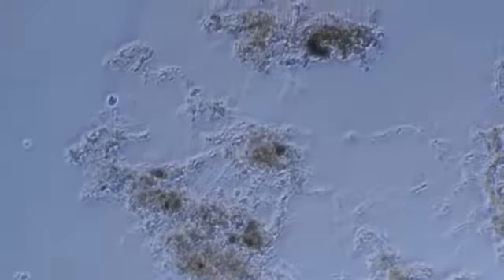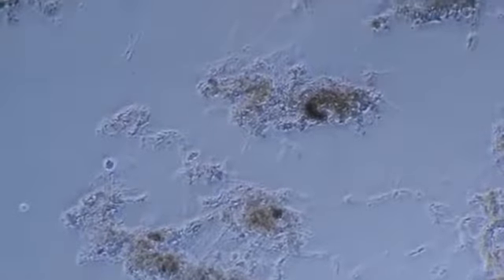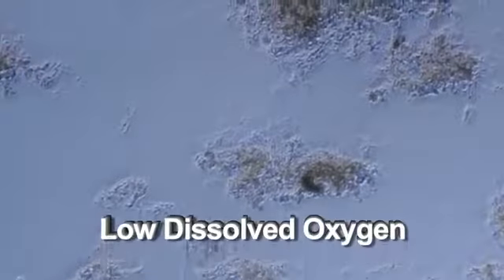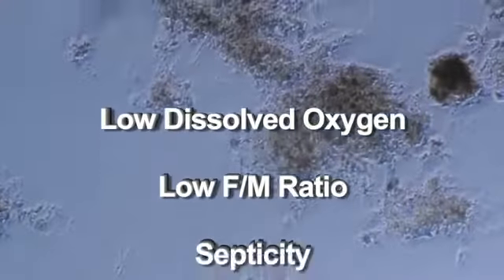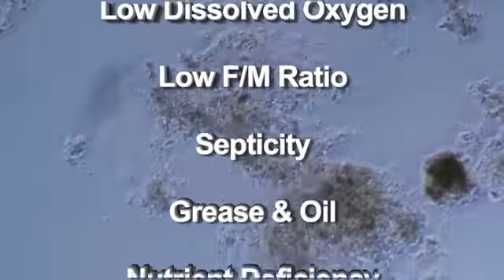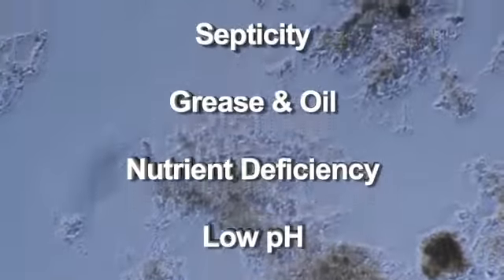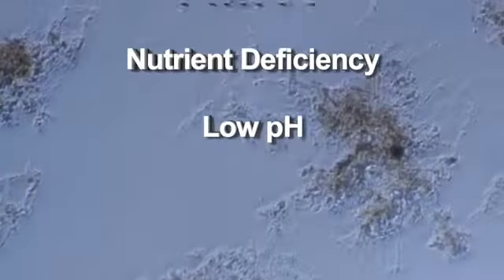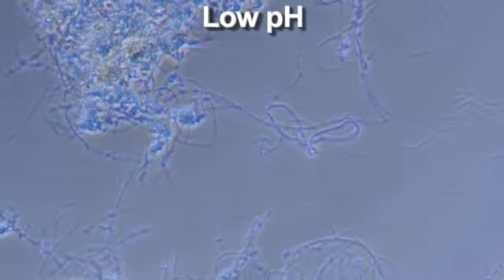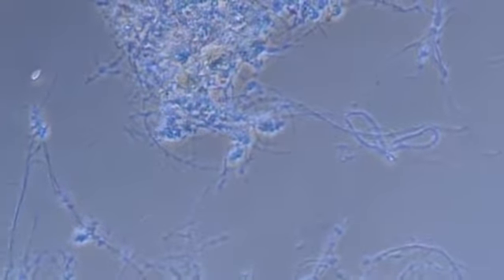As previously touched upon, filament tracking can be another powerful tool to monitor conditions in a wastewater treatment plant. The abundance and type of filaments present can indicate various process conditions such as low dissolved oxygen, low F to M ratio, septicity, excessive grease and oil, nutrient deficiency, and low pH. Tracking filaments requires the use of staining tests, tests for sulfur granules, cell size, and presence of septa, as well as identification of attached growth on the filament.